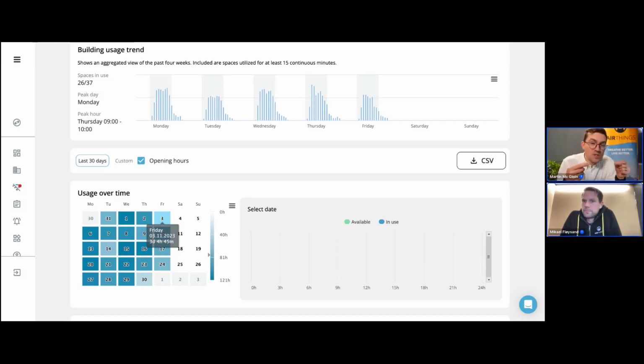A lot of the assumptions we've made with these optimizations is that you probably have a CAV system—constant air volume—with a calendar-based system not based on demand in the space, but more of a 'dumb building' where things are fixed at a certain set point. So you have an assumption about what time in the morning to start ventilating, what time to turn it off in the evening, and then it runs at a fixed air volume throughout the building.